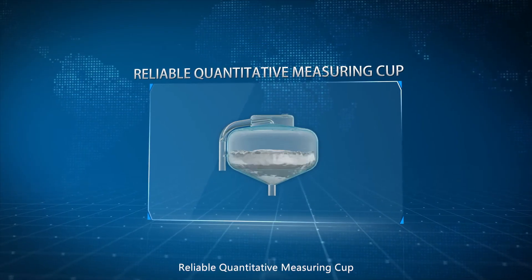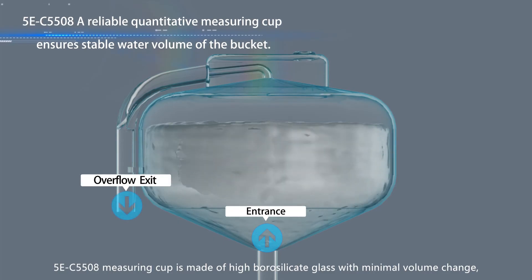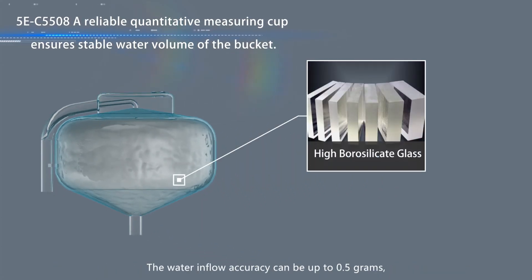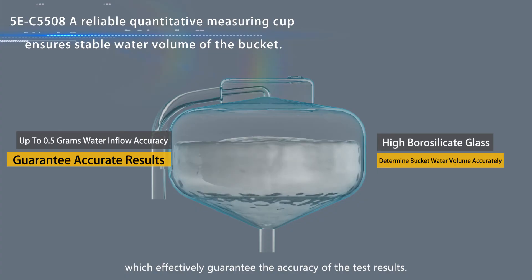Reliable quantitative measuring cup. The 5EC5508 measuring cup is made of high borosilicate glass with minimal volume change, which can accurately determine the water content of the inner bucket. The water inflow accuracy can be up to 0.5 grams, which effectively guarantees the accuracy of the test results.